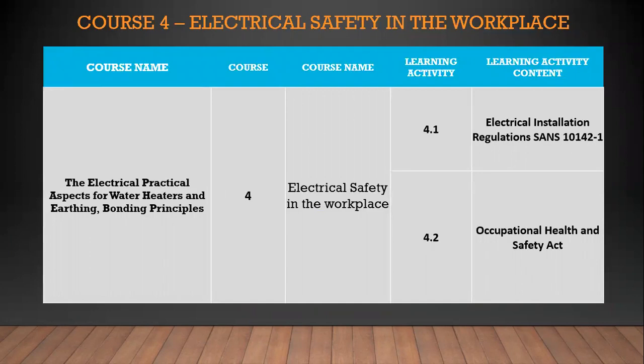Now, ladies and gentlemen, we often hear that people get electrocuted, especially plumbers, or there was an incident or an accident. Some of them are fatal, others are not fatal. And this comes back down to basics. Most of these accidents happen because people are too much in a hurry. They accept that the isolator in the geyser installation inside the roof is actually isolating the circuit, and it's not. Hence the reason you must test and make sure it's safe to work.